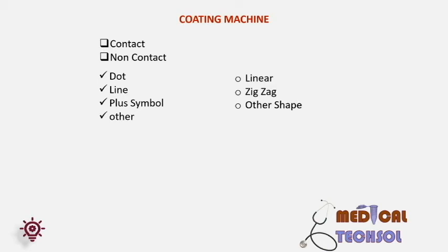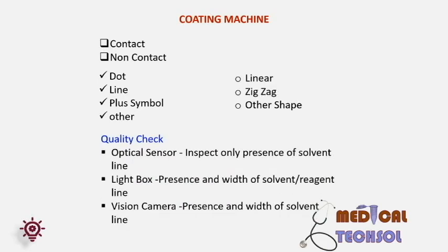Quality checks done for automated and manual coating machines are: first, an optical sensor — inspects only the presence of solvent; second, a light box — checks presence and width of the solvent reagent lines; third, a vision camera — checks presence and width of the solvent lines. Once membranes are dried, it is not possible to check the quality of the line.